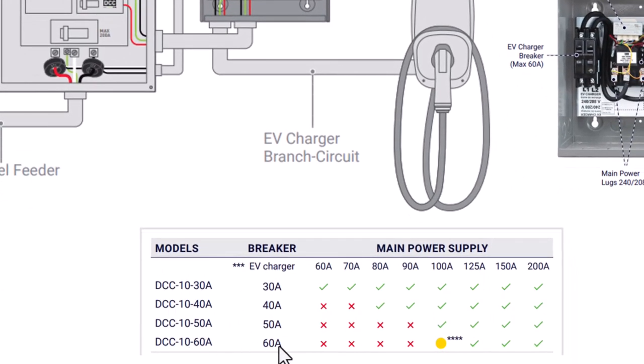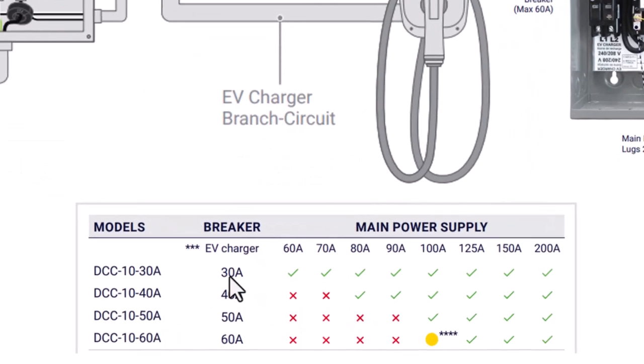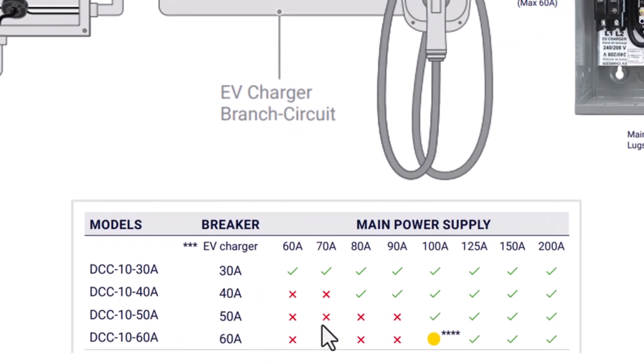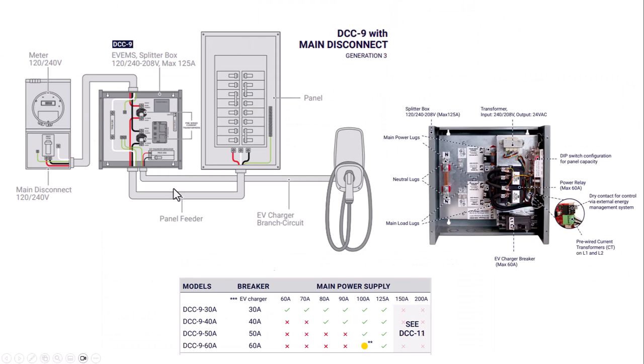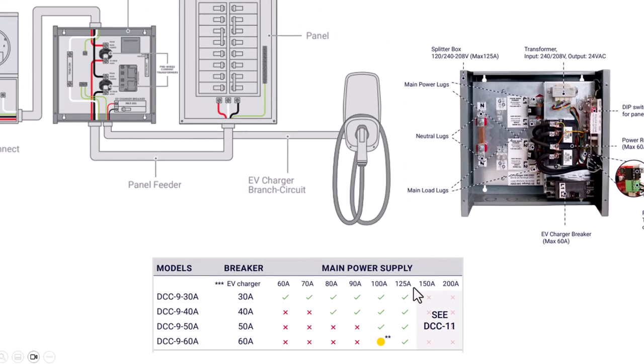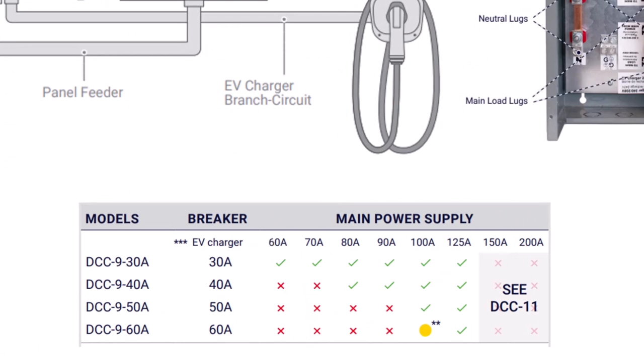And here are the amperages that this box comes with. So it comes in 30, 40, 50, and 60 amps. And it goes up to a main power supply of 200 amps, which is similar to the DCC9. But the DCC9 only goes up to the 125 amps. And if you wanted to go up to the 150 and 200, you would have to go with a DCC11. So that is the difference between the 9 and the 11. And that's just with the rating. So DCC11 can handle 150 and 200. And the 9 handles the rest here. So that's the only difference between the two.